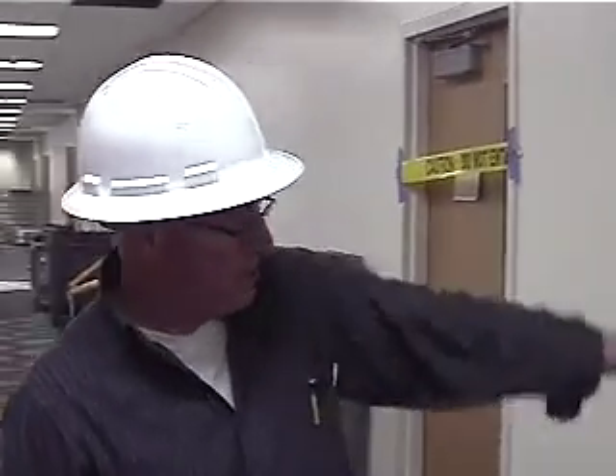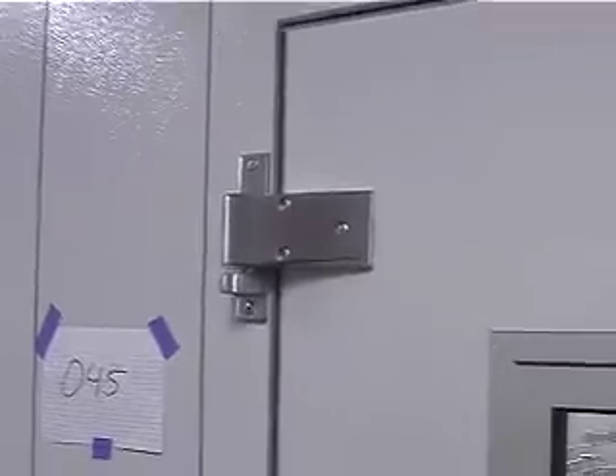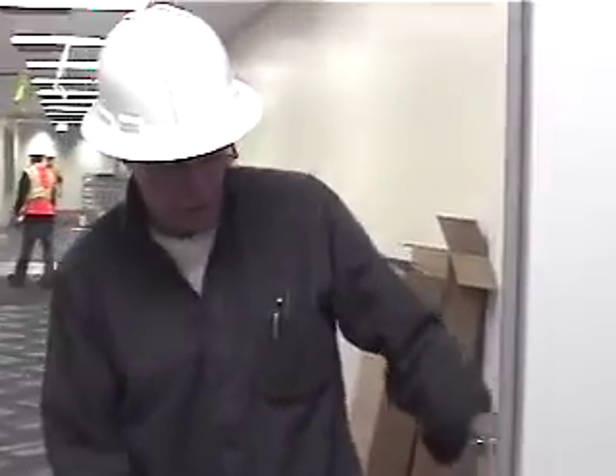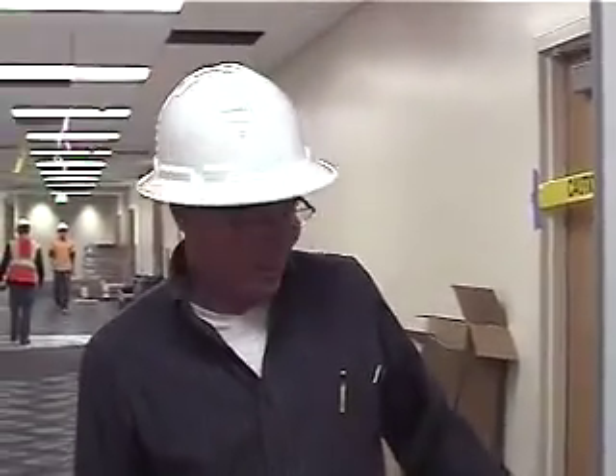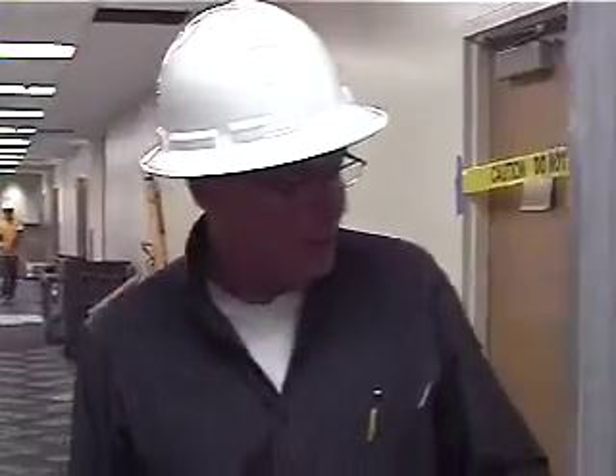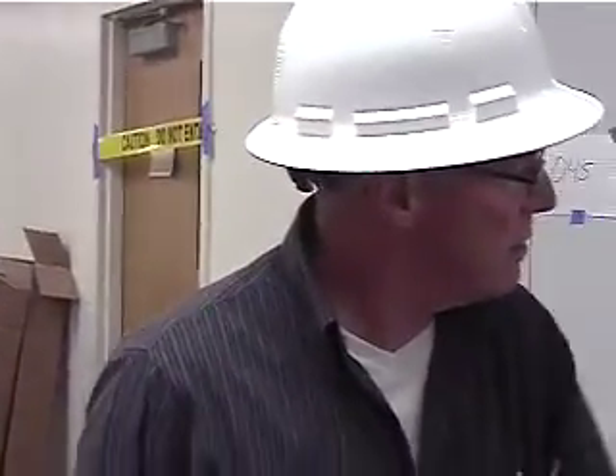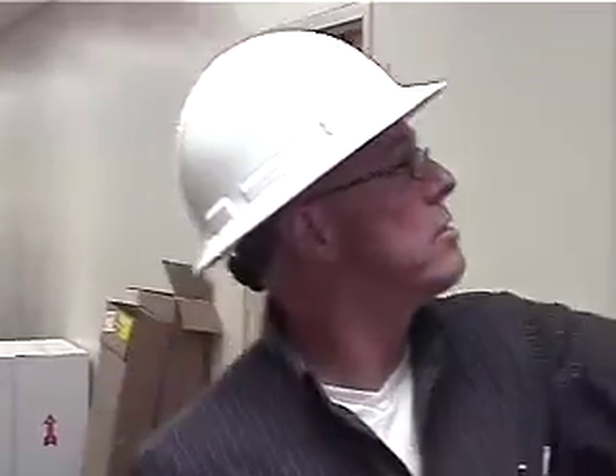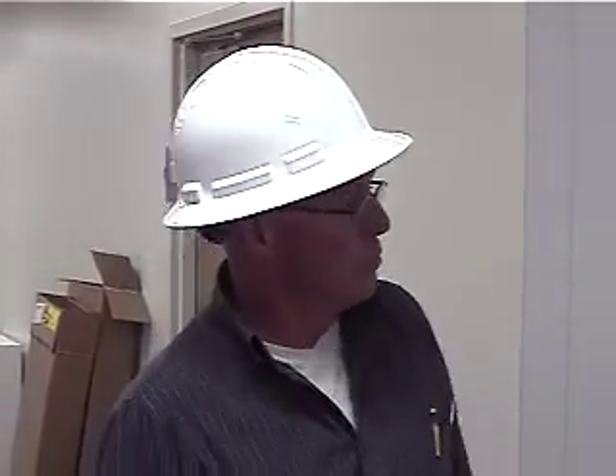Yeah. 3 hinges. If you'll notice, as the cam rises, we've got a little bit more friction out here than we're accustomed to. So it may take a little bit of effort to open that because of that bottom sweeper. But the door actually opens or raises as it opens. And the purpose of that is so if there's anything on the floor that would stop it from opening, it's supposed to rise above it. Once we get down there, it'll self-close. This little device here, its whole purpose in life is to make sure that the door completely closes. The magnetic gasket itself will get a good attraction without it, but you want to make sure it closes.